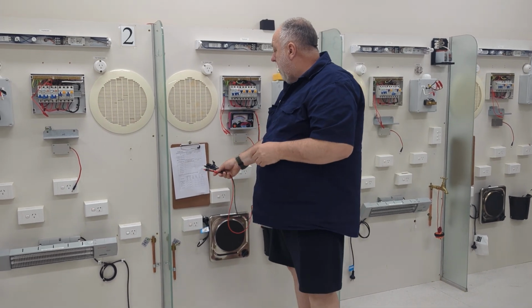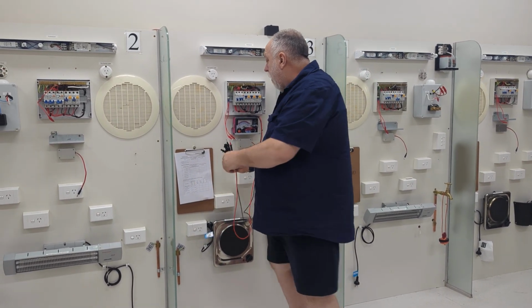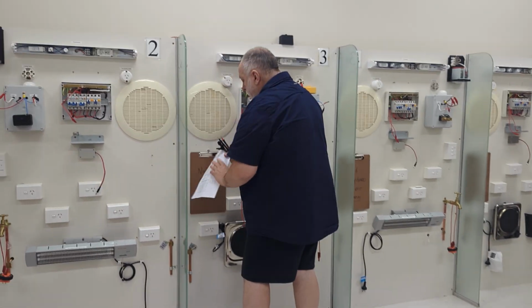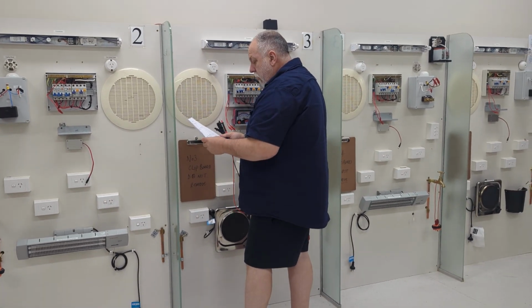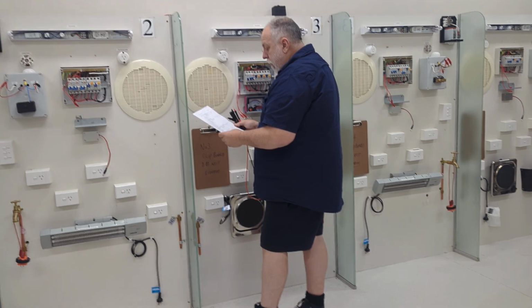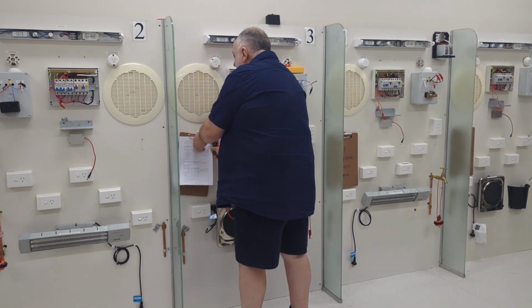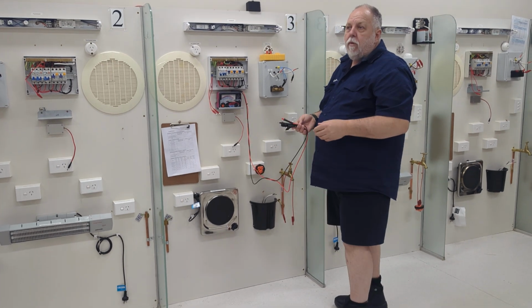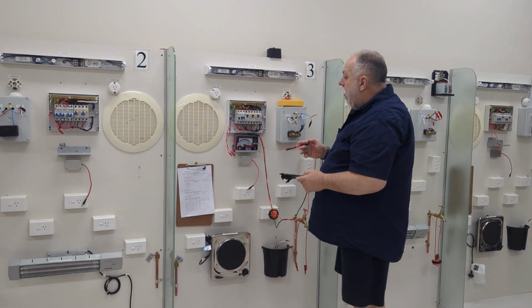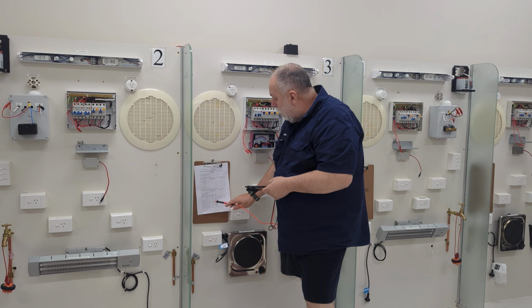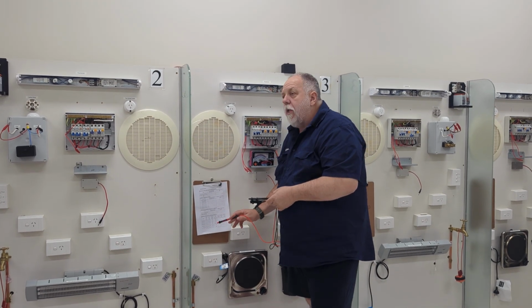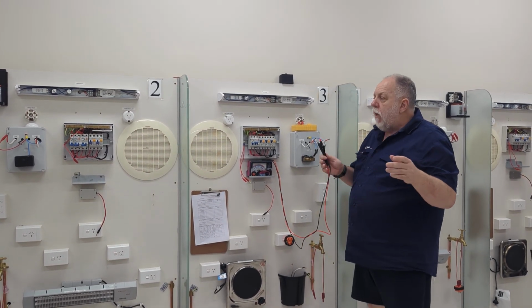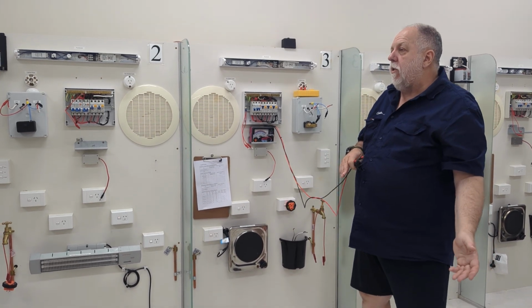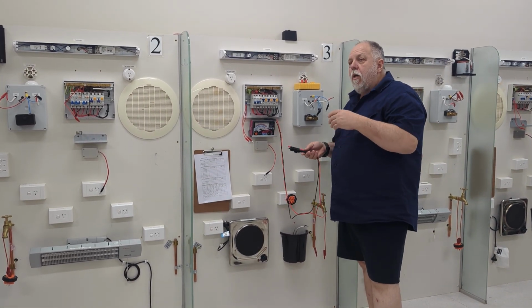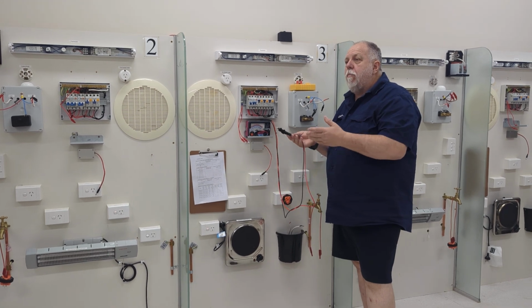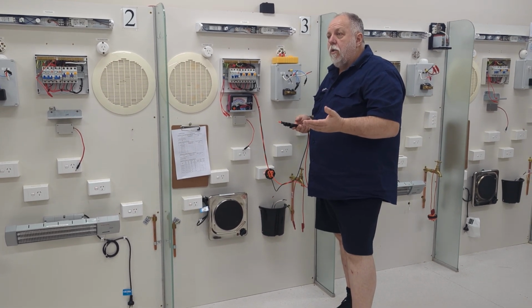The next one I'll talk about is jump down to where it says testing of all subearths. Down there, got insulation resistance, testing of appliance, testing of protective earthing conductors. The reason I say to go into that is to get all the earthing out of the way. Does that make sense? On that sheet, they would have given you the size of the breaker, the resistance of the active. We're actually doing a test similar to the last test we do, which is fault loop impedance. This is kind of the same as fault loop impedance, but they're actually giving us the active conductor size. Do you understand what I'm getting at?